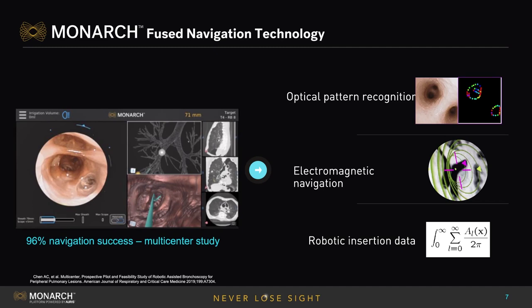What's crucial with any ENB platform is the accuracy of the navigational guidance. One of the values I see in the Monarch system is that, in addition to electromagnetic navigation, this is the only technology that utilizes optical pattern recognition — actually looking at each of the cruxes and subdivisions as you drive the scope out. The technology continuously re-registers at every carina, which further improves navigational accuracy to get you onto the target of concern.